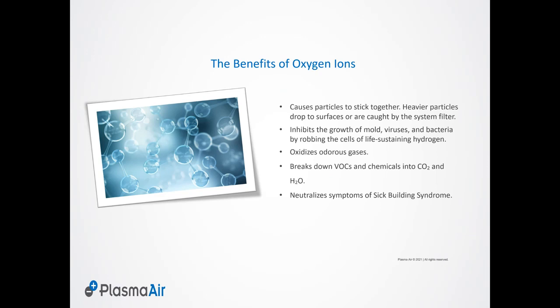The nice part about bipolar ionization is that we don't really care if you have a MERV 8, MERV 10, MERV 13, or HEPA filter. It's going to make every filter work better because the particles are larger. I think ASHRAE really wrapped their arms around the agglomeration aspect of bipolar ionization.